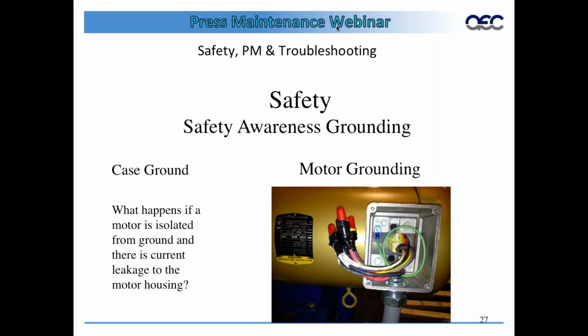Now, at times there can be no metal conduit to the case. You see this picture that has a seal tight to it, which is metal, but it could be that there is no metal conduit to it. So it's just sitting here floating as a metal. And that's another reason that the ground wire is there. So that ground wire, regardless of the motor, the base of it, whether it's sitting on vibration pads, whether it's isolated in any way electrically from ground, then that short current can pass into this green wire and back to a ground source. If you didn't have that and it was isolated, then you may not know that something was at the voltage potential on the outside and it's just waiting for somebody to grab it and then give it a path to ground.